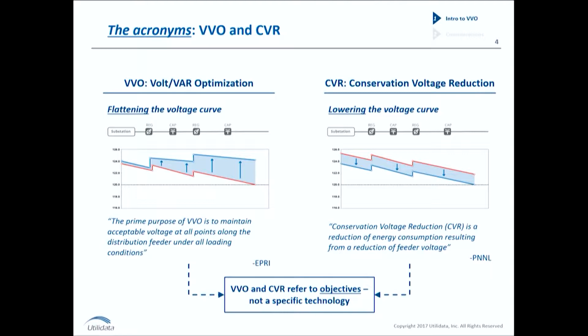CVR is about lowering the curve entirely—dropping voltage while it's still above that minimum bound, like the 114 volts delivered to a residence. It turns out that delivering lower voltage for many loads means things use less energy, and that's your energy efficiency play.